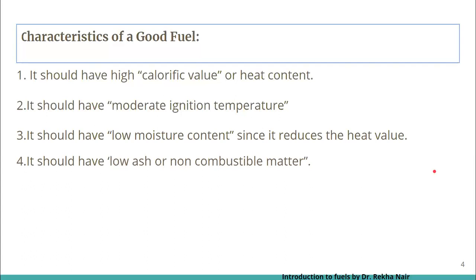A good fuel must have low ash or non-combustible matter. High percentage of ash is undesirable because it does not contribute to the calorific value. Ash, or non-combustible matter, causes reduction in the heat value, increases the cost of fuel, and also causes environmental problems. If in a furnace, the ash may restrict the passage of air and lower the rate of combustion.